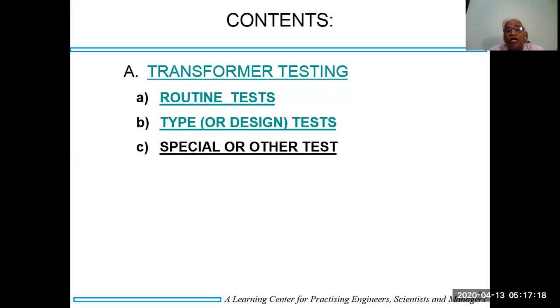Now, what is meant by a routine test? A routine test is done on all the pieces manufactured. Whereas a type test or a design test is, if you are buying 100 transformers, he will test one transformer. If you need some of the other tests, called special and other tests, the seller will charge for them and you have to pay for them also. One more important thing: whatever certificates are given to you, you have to keep the certificates till the end of the transformer life. Many parameters you have to measure and test at frequent intervals, to see that the parameters remain the same throughout the life of the transformer.